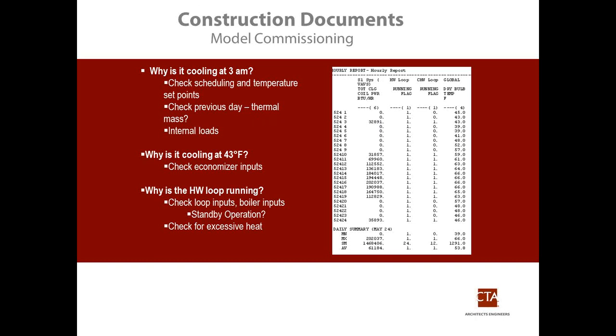And the other thing is, why is it cooling at 43 degrees? Shouldn't our economizer be taking care of that? Maybe it's an IT room or something on that chilled water loop, but it's something you need to look at. And then you see the heating water loop running all the time. It's probably not ideal. Maybe that's just the way it has to be, but check your inputs there.